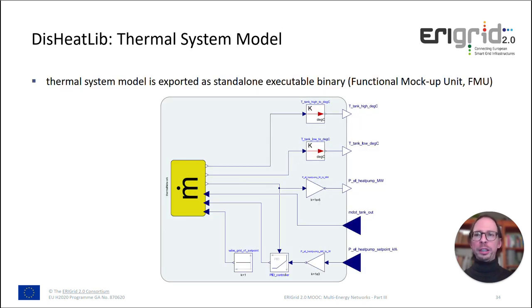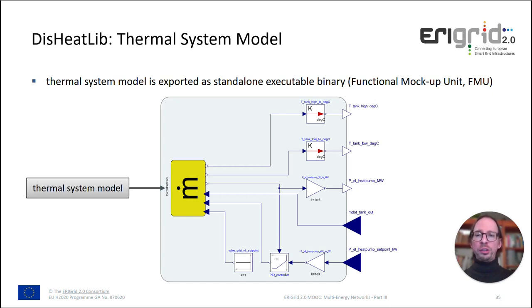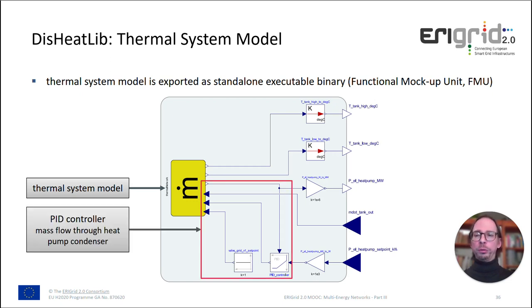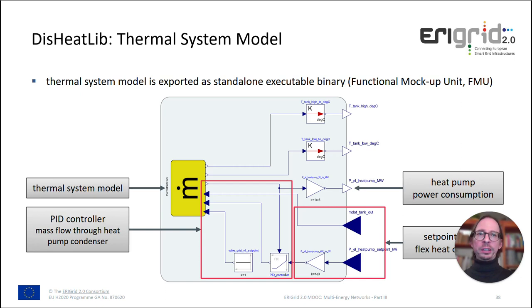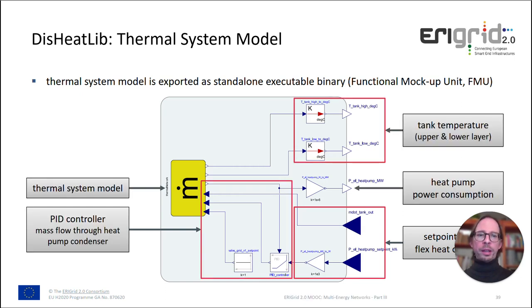To make these models available for the co-simulation, you can export them as standalone executables — so-called functional mock-up units or FMUs. The system model is used as an individual block, augmented with a PID controller for the mass flow through the heat pump condenser. It is also augmented with inputs for the setpoint from the flex-heat controller, and outputs that go to the flex-heat controller and the voltage controller — specifically the heat pump power consumption and tank temperature.